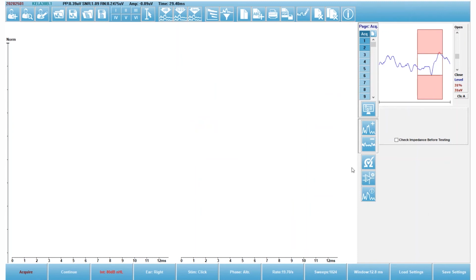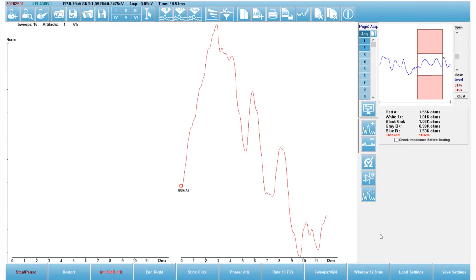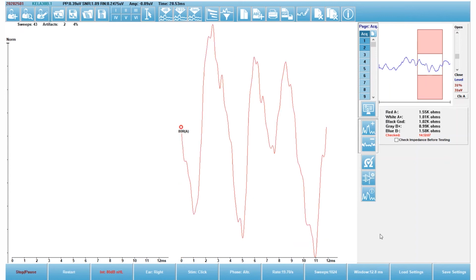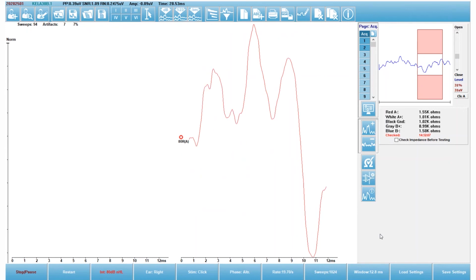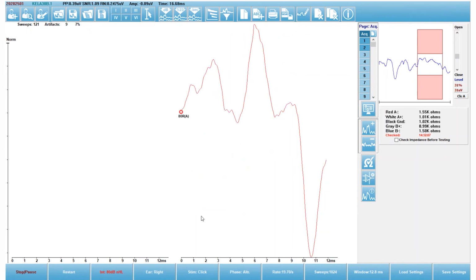Before I get started, I want to see what my impedance readings are. I'm using the 4-lead snap cable. And once those appear, those look pretty good. They're under 5 kilo ohms, so I'm good to go. To start the collection, I'm going to click on the Acquire icon. My right ear test is beginning.